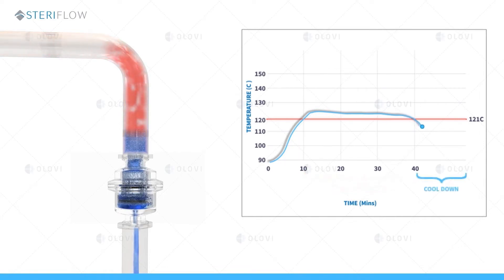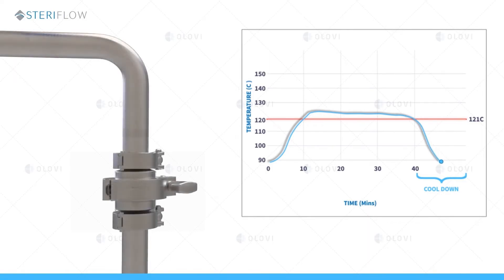After the 30 minute temperature hold period, the clean steam supply will be shut off and all condensate will drain from the piping system. Some end users will then introduce room temperature clean compressed air or nitrogen to force all traces of water from the system.